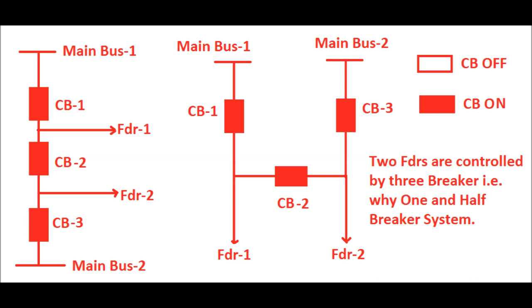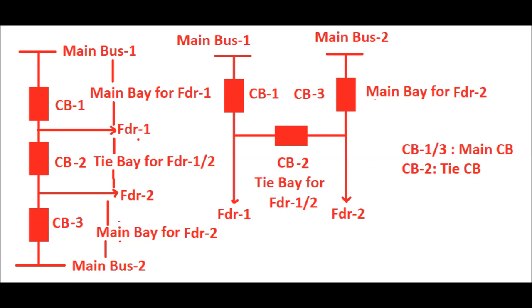Since two feeders are controlled by three circuit breakers, this system is called the one and half breaker system. CB1 and CB3 are the main bus side circuit breakers. CB1 is the main bus 1 side circuit breaker and CB3 is the main bus 2 side circuit breaker. The portion between feeder 1 and main bus 1 is called the main bay for feeder 1, and the portion between feeder 2 and main bus 2 is called the main bay for feeder 2. The portion of the bay in between feeder 1 and feeder 2 is called the tie bay, and the circuit breaker connected between feeder 1 and feeder 2 is called the tie circuit breaker or tie CB.